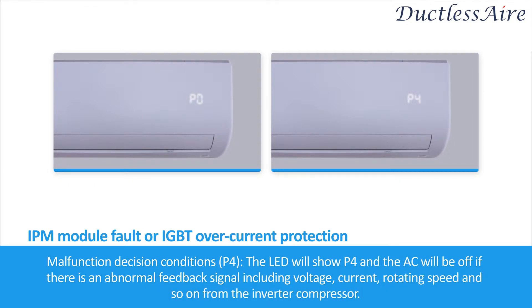Malfunction decision condition for P4: the LED will show P4 and the air conditioner will be off if there is an abnormal feedback signal — including voltage, currents, rotating speed, and so on — from the inverter compressor.